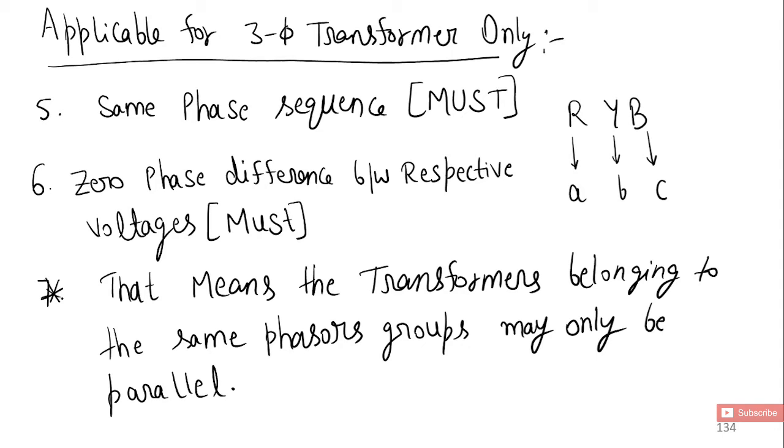Applicable for three-phase transformer only, there are a few conditions. Same phase sequence - this is must. Phase sequence may be R Y B or A B C. If A B C means B C A, this is also same, or you can say C A B. This is same phase sequence.